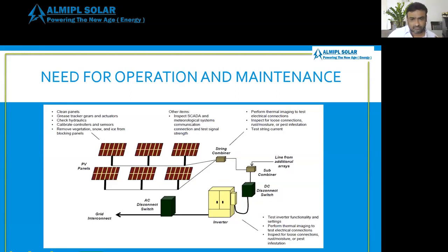Other items. SCADA. Inspect the SCADA, the supervisory control and data acquisition. This is the SCADA, and the meteorological system communication: connect and test signal strength. Perform thermal images to test electrical connections, inspect for loose connections, rust, moisture or pest infestation, test string current. So the string combiner, lines from the additional array, sub combiner, DC disconnect.